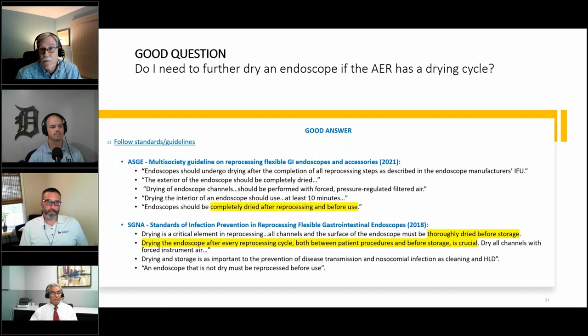Where do the current guidelines stand? On the screen, you see a few examples here. The multi-society guideline speaks to the need for drying after the completion of all reprocessing steps. This means the exterior as well as the channels. They reference, quote, forced pressure regulated filtered air for at least 10 minutes. SGNA similarly highlights the need for thorough drying before storage or reuse. They emphasize that an endoscope that's not dry must be reprocessed before use. The common thread here is active filtered air drying every time, whether the scope's headed for storage or to the next procedure. Next slide, please, Seth.